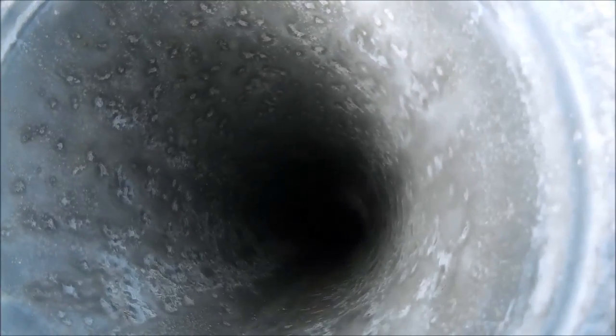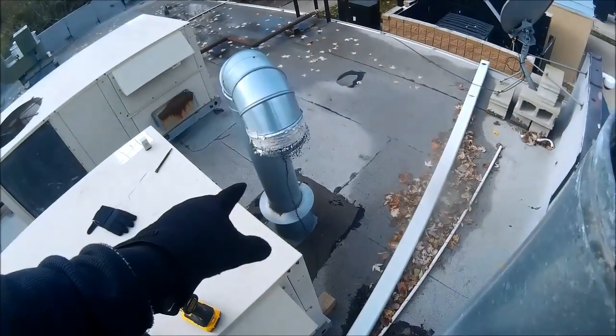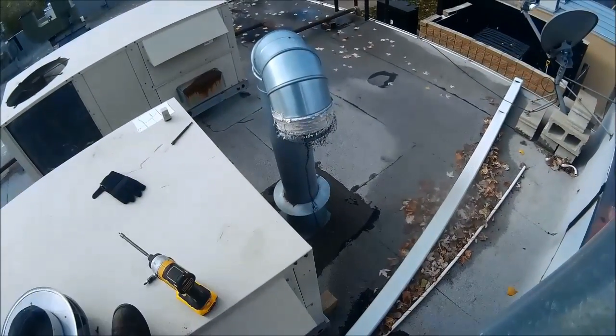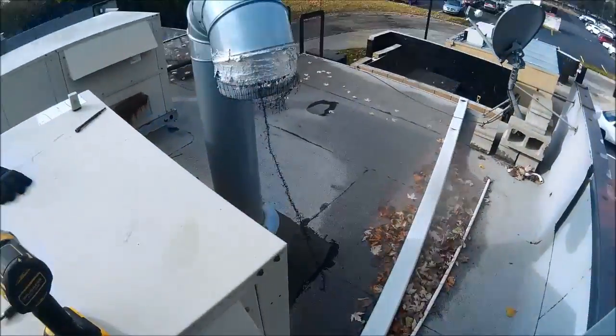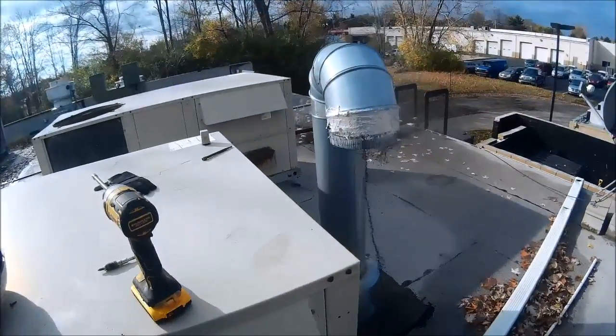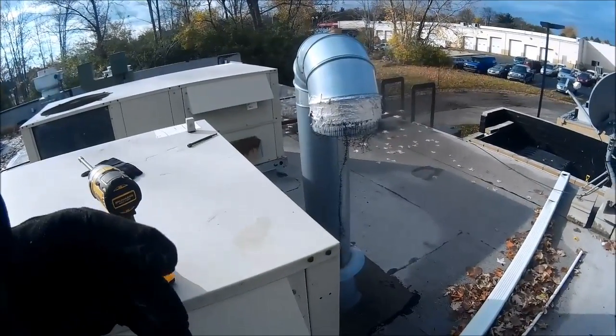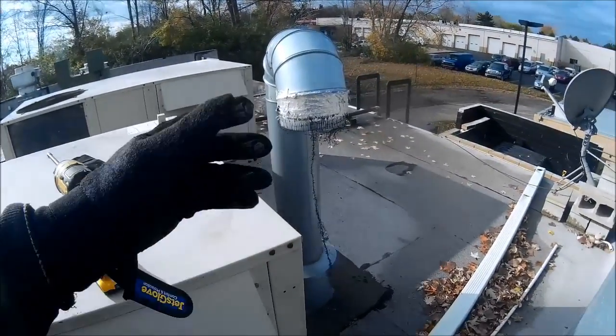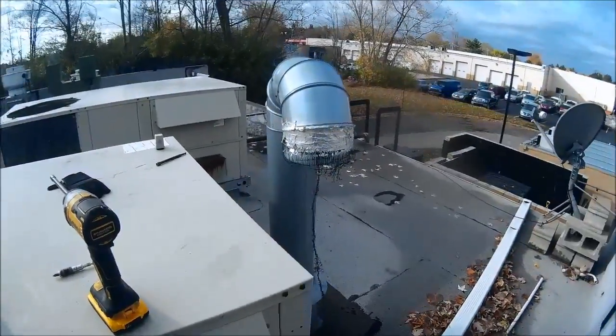If you look down my flue, I'm clear. That's my air intake for the room — combustion air into the room. They had a jug or something plugged up in it. The second time I started it, after letting the analyzer sit in there, we got 1,500 parts per million coming off that heater because it's not venting. We've got some negative pressure issues in this restaurant with this natural draft appliance.